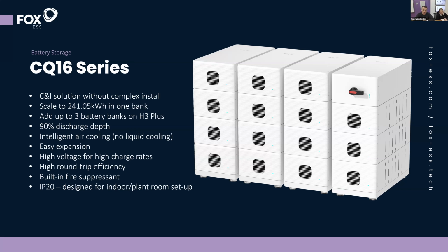You can see on the image there, there's forced ventilation through fans. So they're an IP20 solution. It's important to stress that. So these are an indoor solution. They would have to go into a plant room, or if it wasn't possible to put it in the main building, you could put these in some sort of shipping container outside, but they do need to be protected because they're not protected against rain and water ingress beyond the IP20 protection.